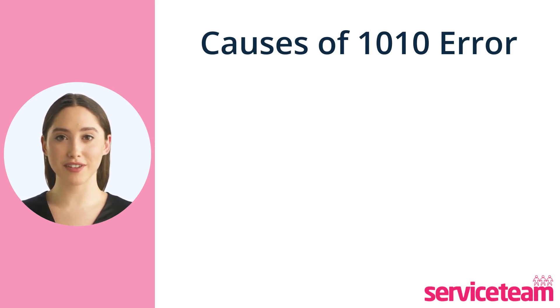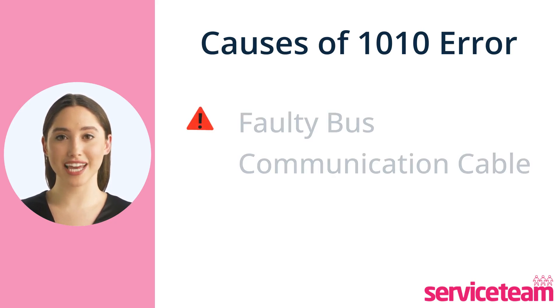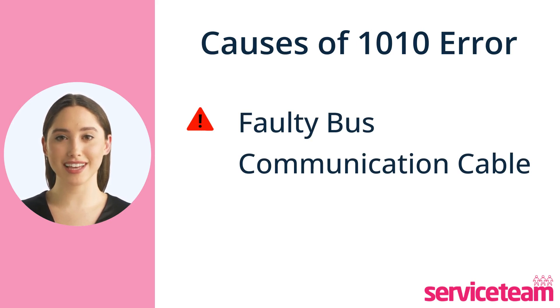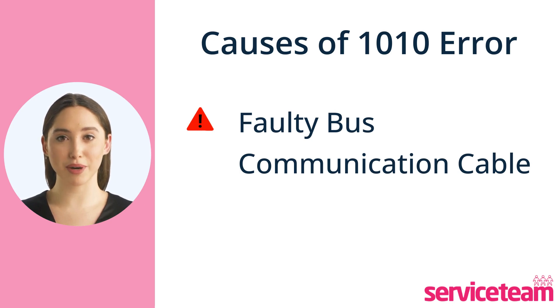There might be one of the following issues. The most common cause of this issue is the faulty bus communication cable, which is responsible for transmitting digital signals between boiler components and sensors within the boiler system. When the EMS bus isn't connected properly or is damaged, it disrupts communication within the system.